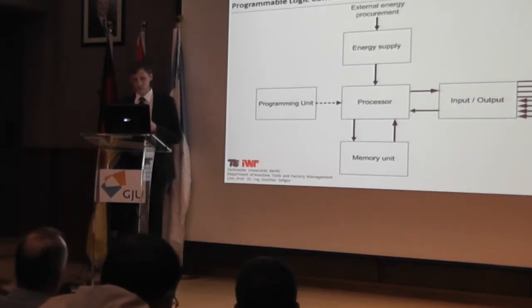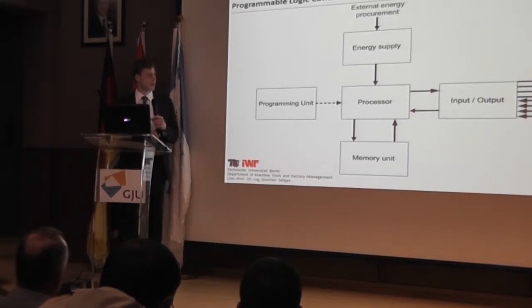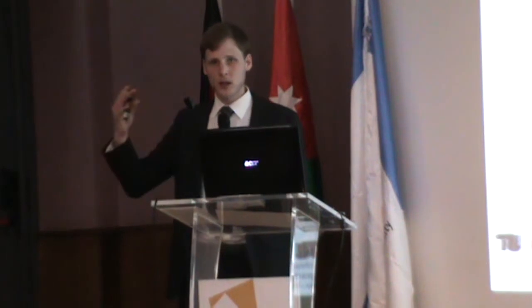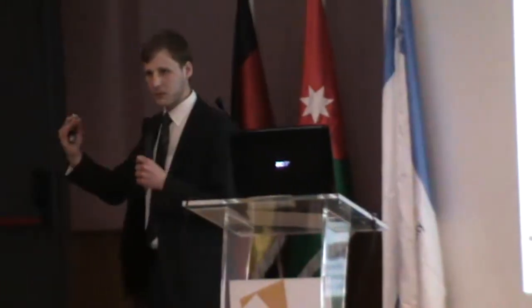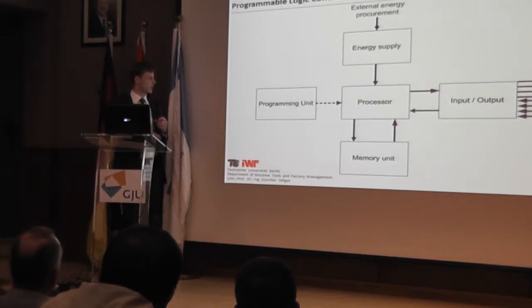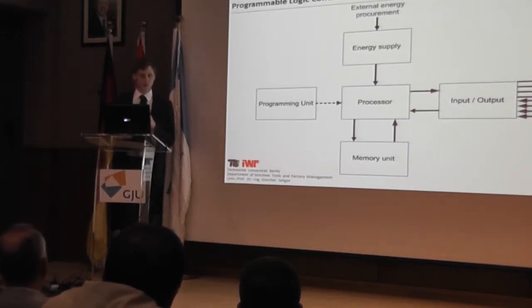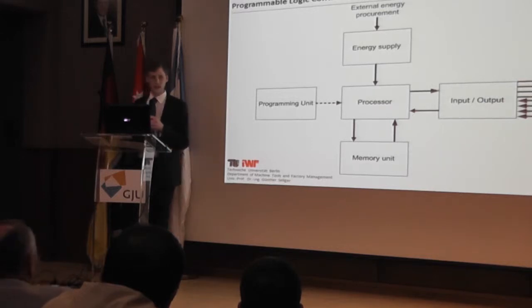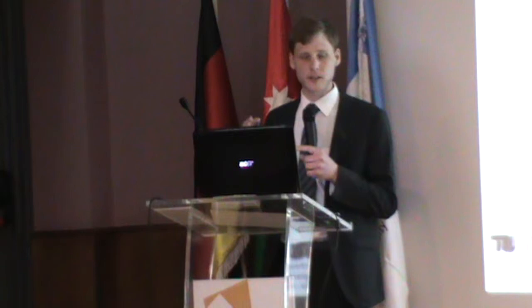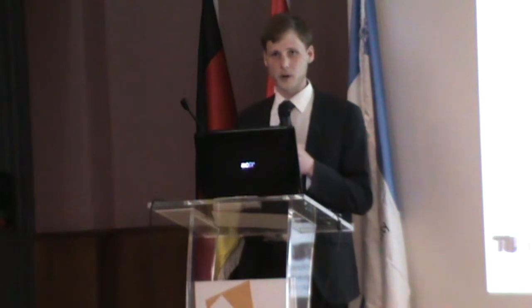A PLC from the hardware side has inputs and outputs. Outputs mean I give a signal to an actuator, which reacts in the corresponding way. Inputs come from a sensor, which delivers a signal that is then processed. A PLC needs energy, has a memory unit, and a programming unit. Due to historical development, there are different kinds of PLCs — at the beginning they were hardwired, but meanwhile we can talk about soft PLCs, where the control and processing is done directly by industrial computers.